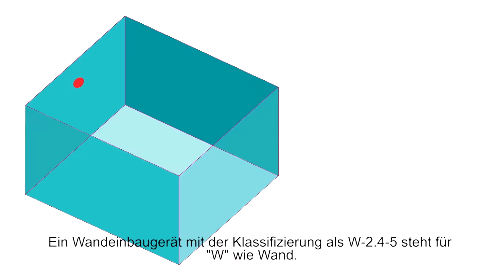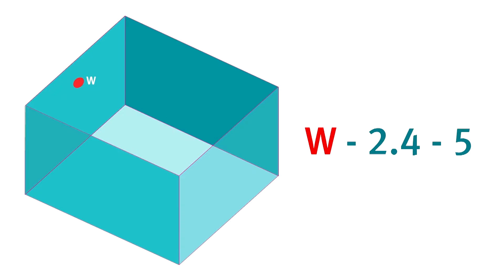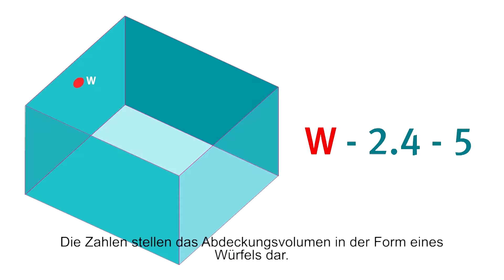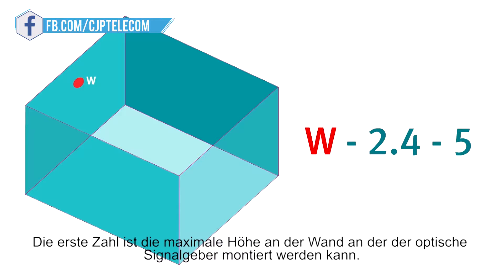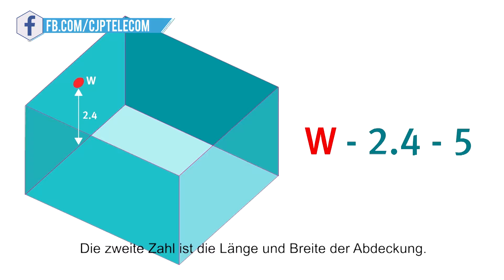A wall mounted VAD might be rated W2.4 5, where W stands for wall. The numbers again represent the coverage volume, this time in the shape of a cube, where the first number is the maximum height on the wall that the VAD can be mounted and the second number is the length and width of the coverage.